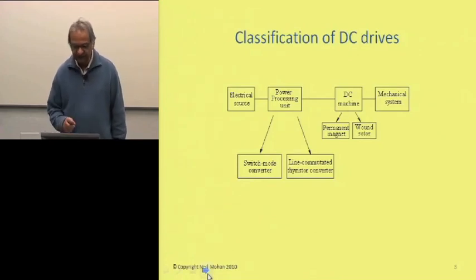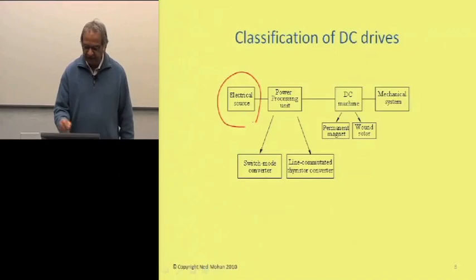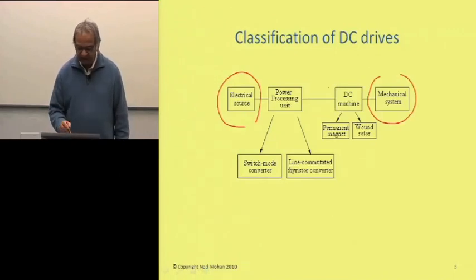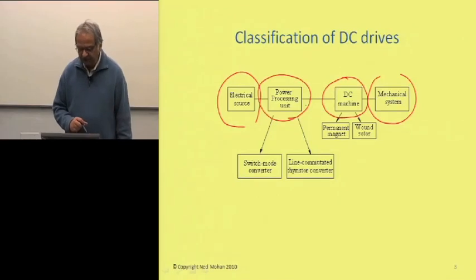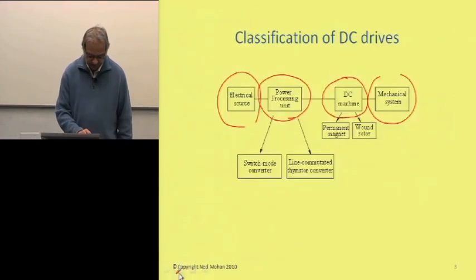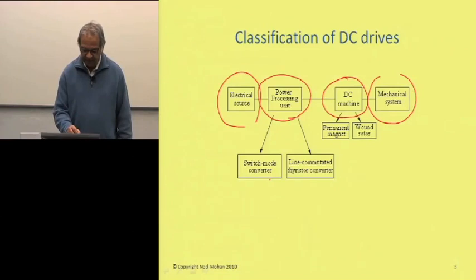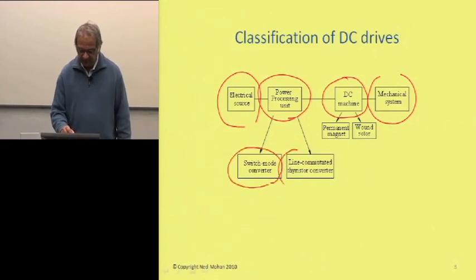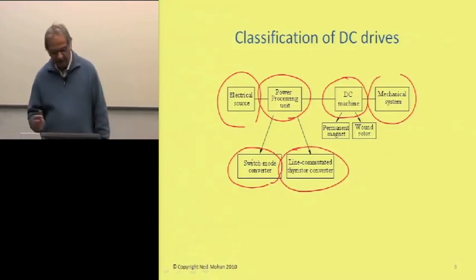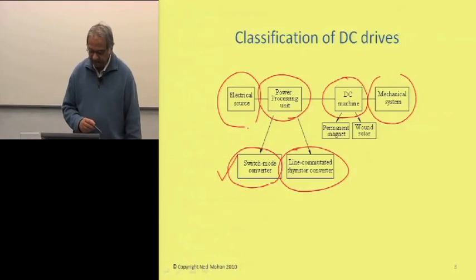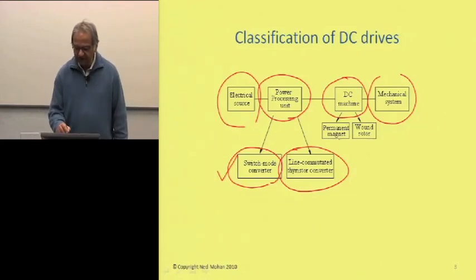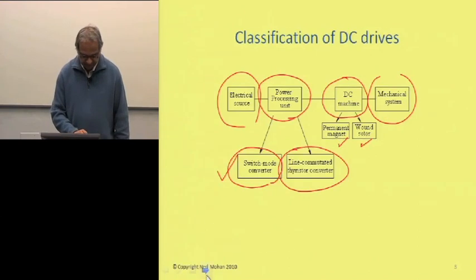In terms of classifying DC drives, we have an electrical source and a mechanical system, and between the two we have a DC machine and a power processing unit. This power processing unit may be made up of switch mode converters or line-commutated thyristor converters. By and large, now it's really the switch mode converter that is used. As far as the DC machine is concerned, it may have permanent magnets or it could have a wound field, as you'll see in the next slide.